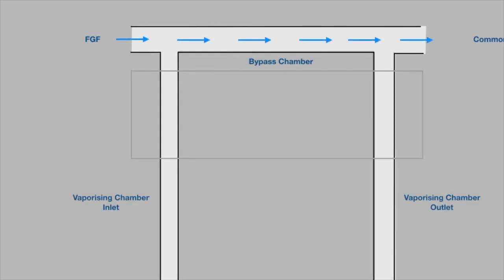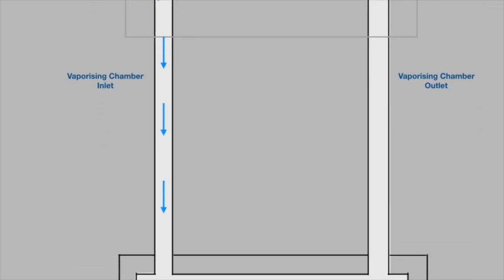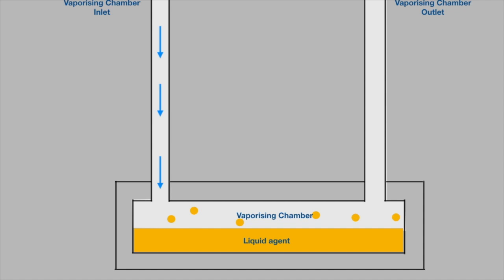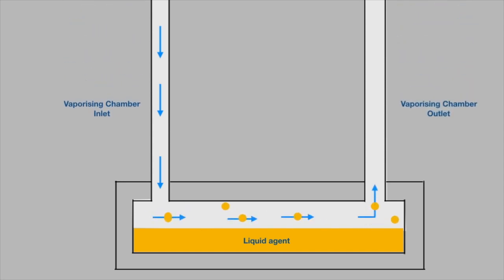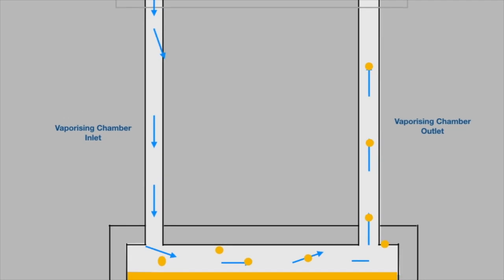See the fresh gas flow flowing through the bypass chamber. Once the dial is opened, a part of the fresh gas flow flows into the vaporizing chamber inlet. That part of the fresh gas flow reaches the vaporizing chamber and carries vapor molecules to the outlet through the vaporizing chamber outlet, where it joins the common gas outlet.